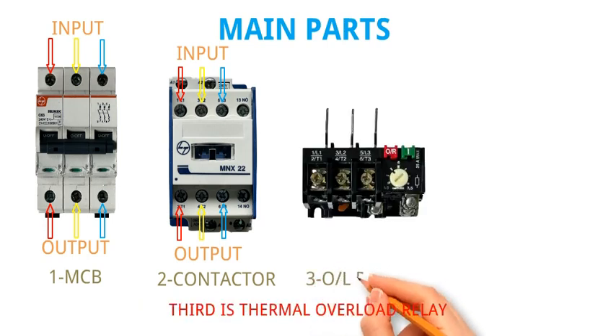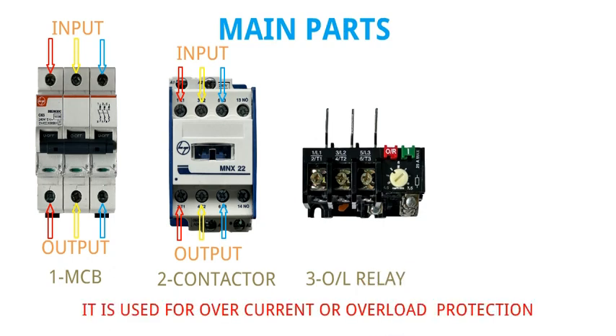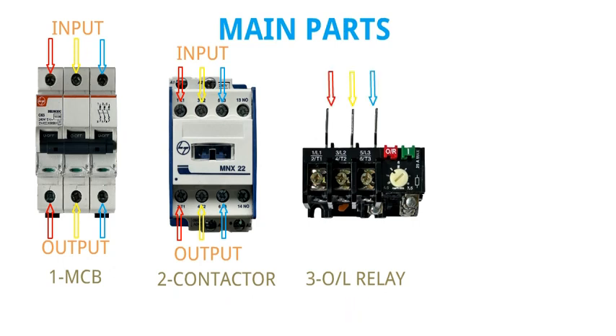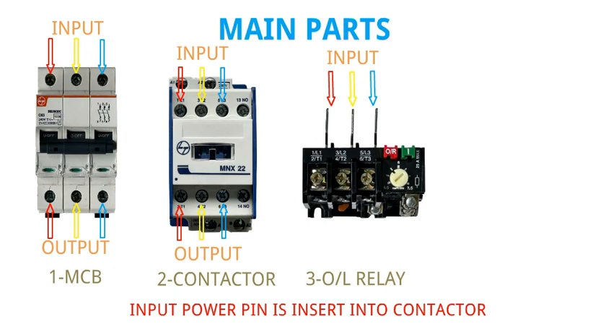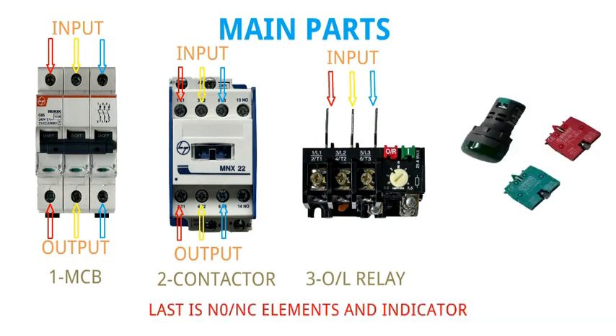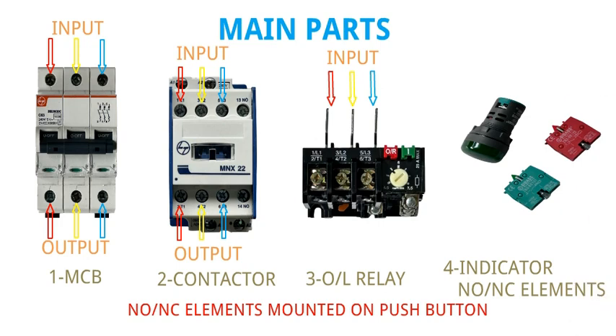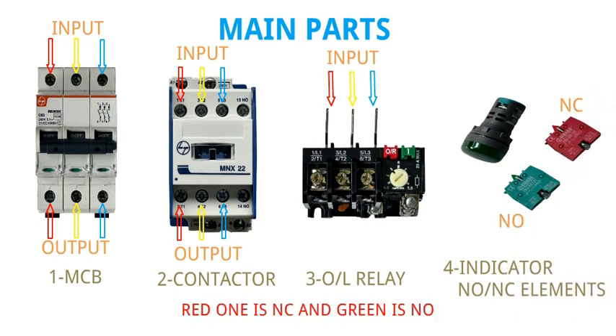Third is the thermal overload relay. It is used for overcurrent or overload protection. It also has six power and some control terminals. The input power pin is inserted into the contactor. Last are the NO/NC elements and indicator — NO/NC elements are mounted on the push button. The red one is NC and the green is NO.